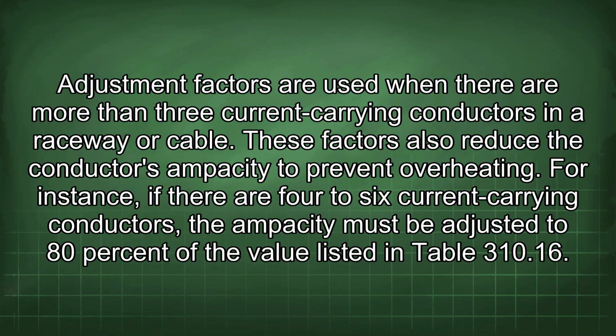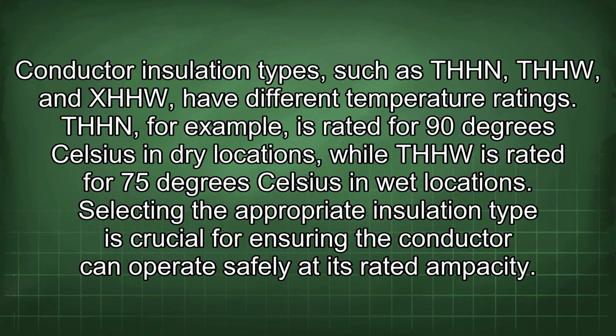listed in Table 310.16. Conductor insulation types, such as THHN, THHW, and XHHW, have different temperature ratings. THHN, for example, is rated for 90 degrees Celsius in dry locations, while THHW is rated for 75 degrees Celsius in wet locations.